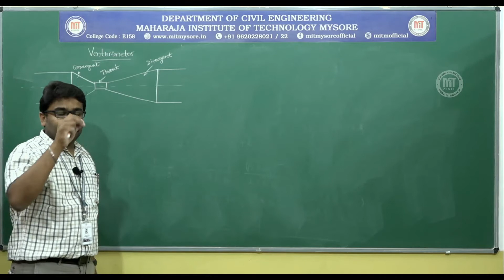Now, how do I measure the discharge using this? The simplest principle involved here is, when water or any liquid is flowing in the pipe, it is led into the venturimeter through the convergent, and then it flows through the throat and then enlarges back into the pipe dimension. What actually happens is there is a change in the dimension of the flow cross section. If the cross section is reduced, that means area is reduced, the velocity will increase but pressure will also decrease. And when area is increased, pressure also increases but velocity decreases.